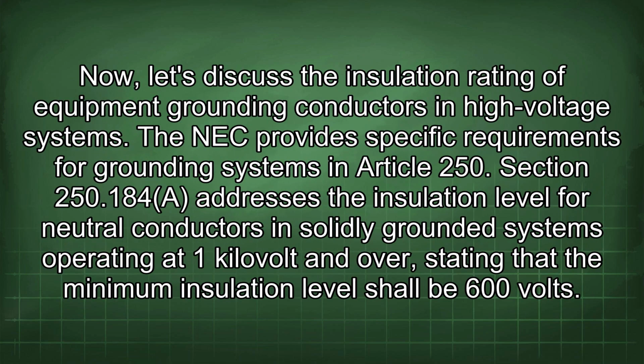alone. Now let's discuss the insulation rating of equipment grounding conductors in high voltage systems. The NEC provides specific requirements for grounding systems in Article 250. Section 250.184 addresses the insulation level for neutral conductors in solidly grounded systems operating at 1 kV and over, stating that the minimum insulation level shall be 600 volts.